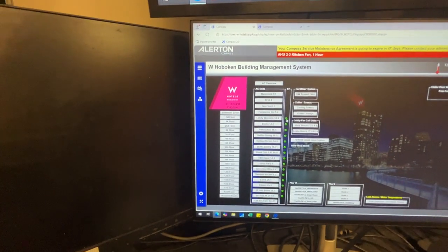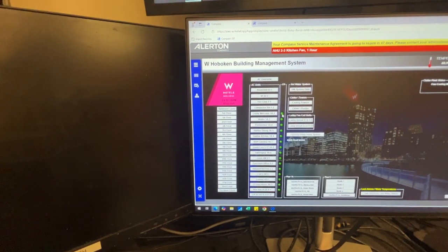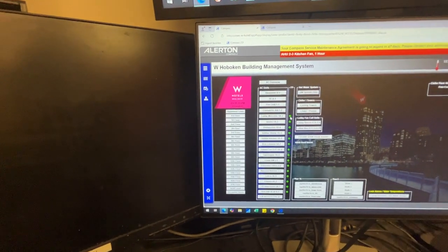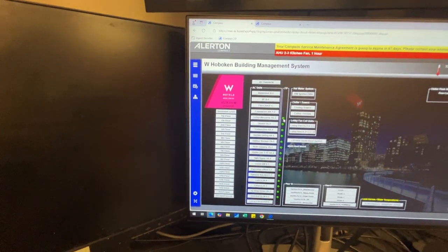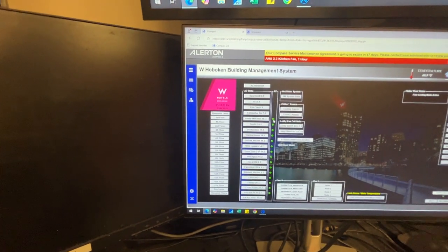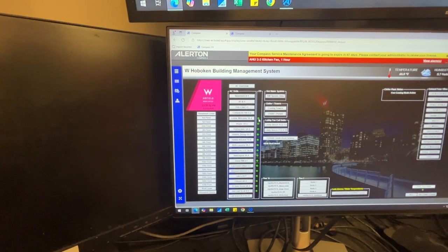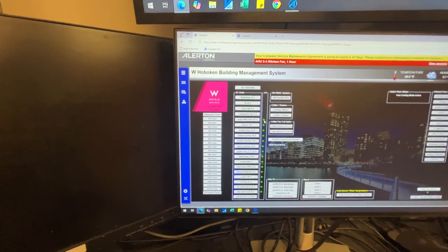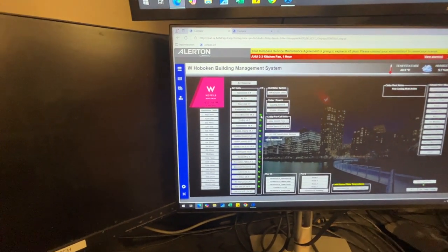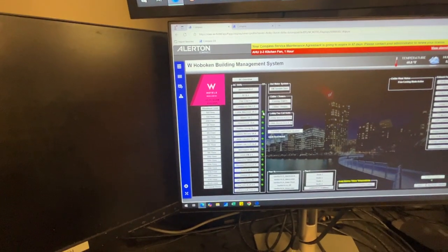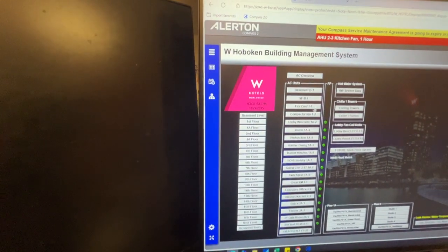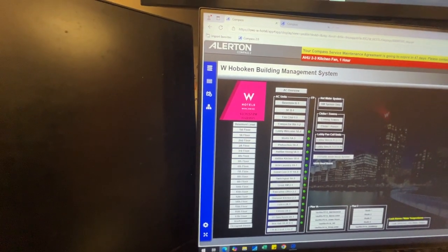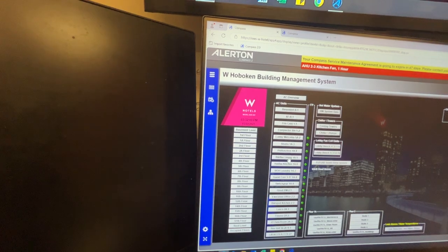During the wintertime, there's nothing you can do if one of those trips and it's colder than like 30 degrees out. You should not be constantly having the team reset them just because there's a group in the ballroom. It's possible that your return fan's not working or your outside air damper is stuck open, which made it freeze in the first place. But anyways, these are all freeze points. As far as the units, pretty self-explanatory. I don't have anything to really go over on those.